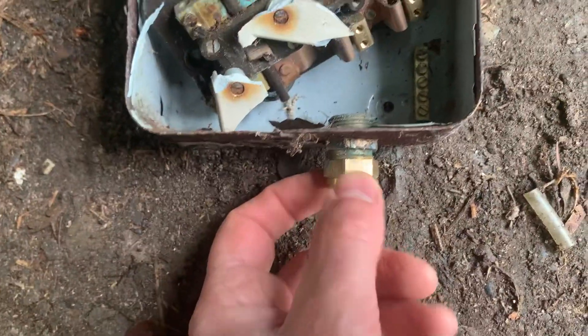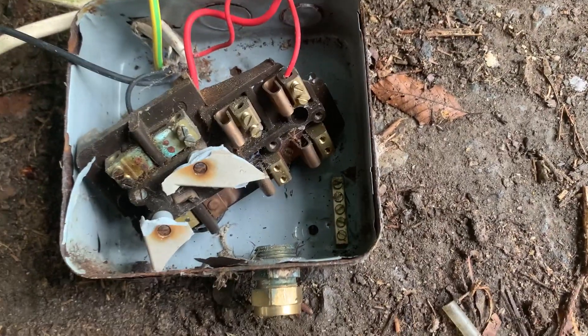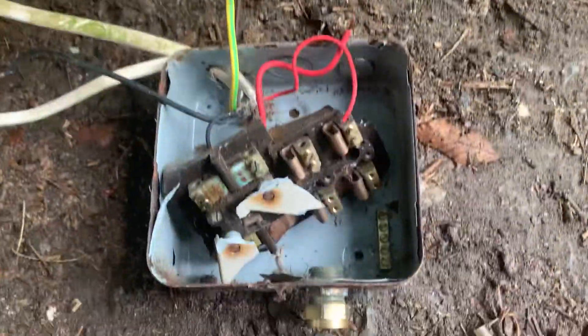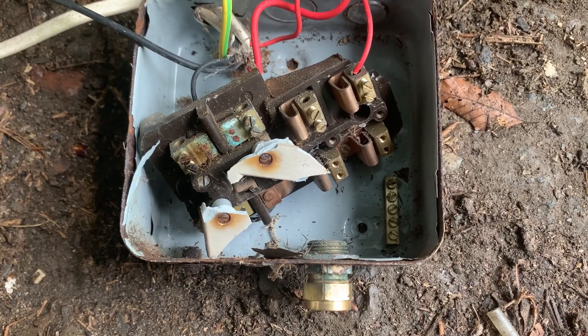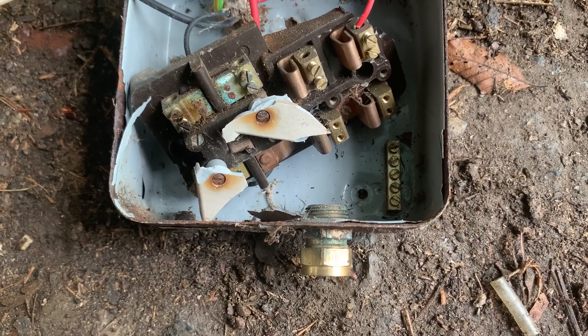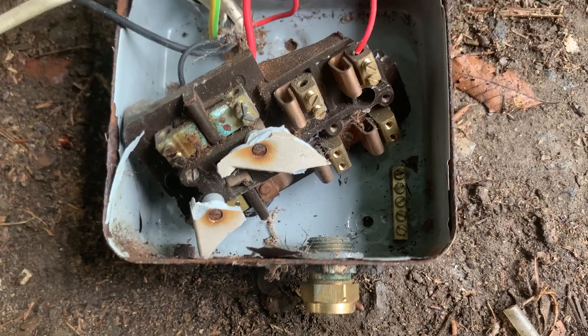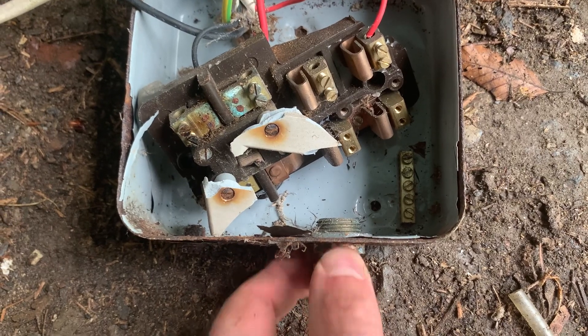So that's how that works. And I'm thinking, well, I don't really want to have to dig up the wire which goes all the way back to the house in order to put in a new one with an earth. I guess I could earth this consumer unit here in the shed with some kind of ground spike or something. Or I could just carry on using this brass fitting. So I've ordered a new consumer unit with a metal box, and when that arrives I might have a look inside and see whether it might be applicable to reuse this fitting, or maybe get another one.